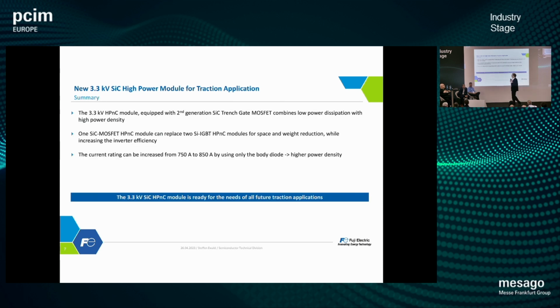To summarize, the 3.3 kV module is equipped with our second generation trench MOSFETs without Schottky barrier diode, combining very low loss dissipation with high power density. With one module equipped with silicon carbide chips, we are able to replace two modules in parallel with silicon IGBTs inside. By leaving out the Schottky barrier diodes, we were able to increase the current rating in this package from 750 ampere to 850 ampere.